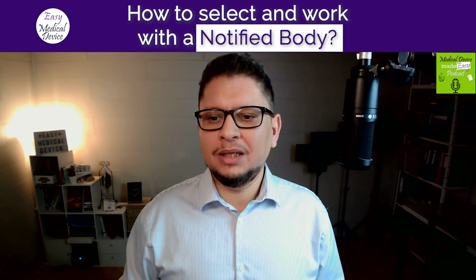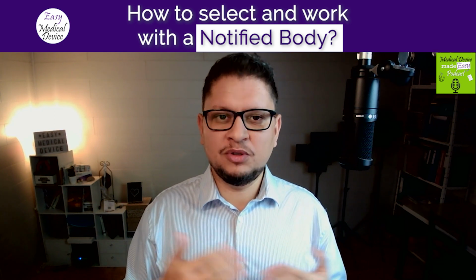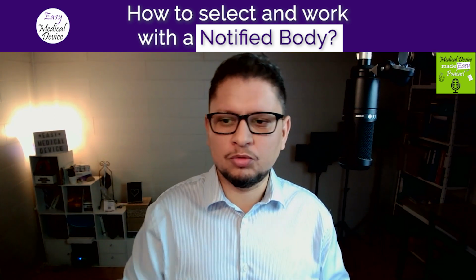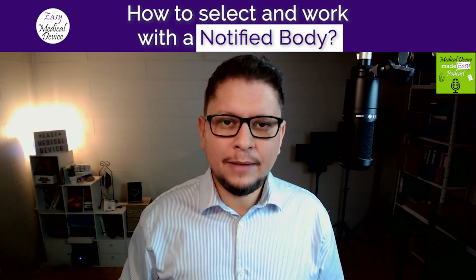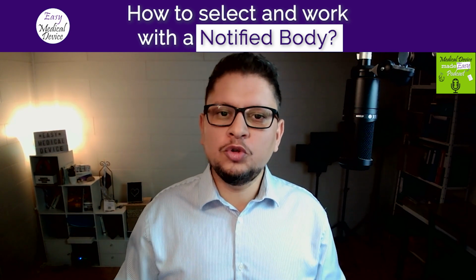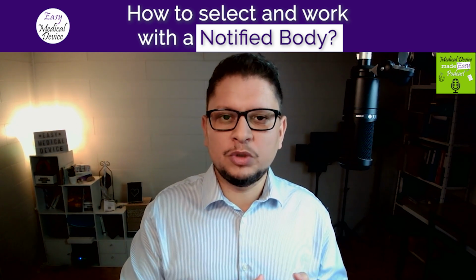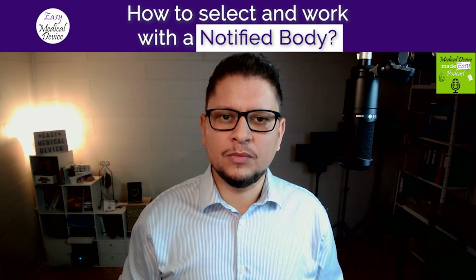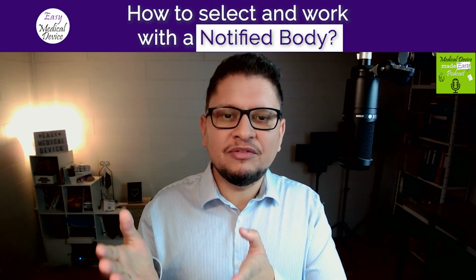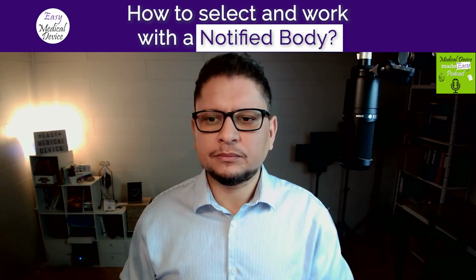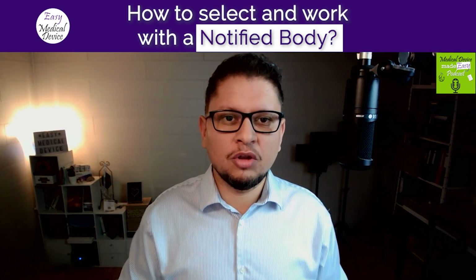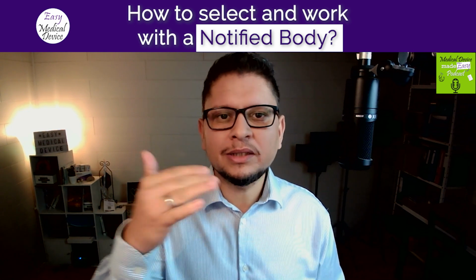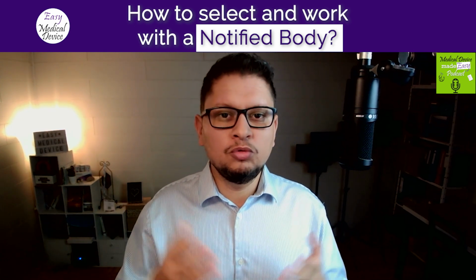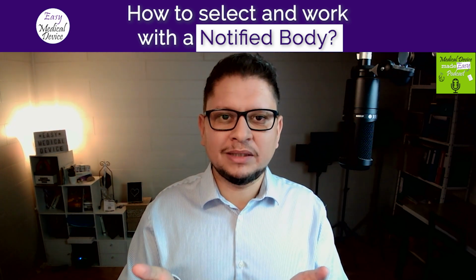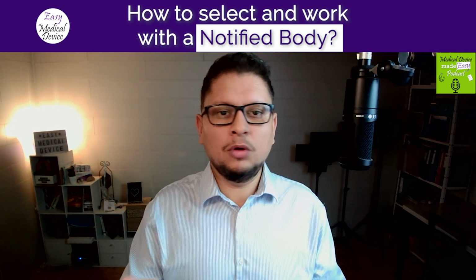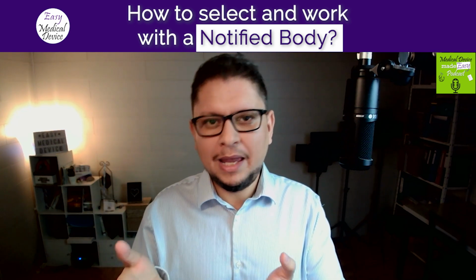For example, if you are a class 1 device, so it's self-certification, there is no need of notified body, so this is your conformity assessment route. If you are under class 2A, you have three choices. Or you go through Annex 9, which is mainly the review of your quality management system and technical file, or you go through Annex 11 Part A or Annex 11 Part B, which is another route that you can check on the EU MDR, where it tells you exactly what is included inside each route. So you read the Annex 9 or Annex 11 Part A or Annex 11 Part B, and you say, oh, I want to be audited through Annex 11 Part A or Part B.